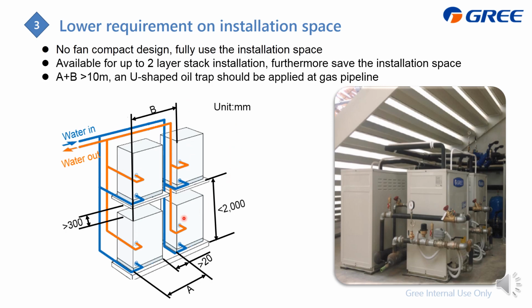In this case, you just need to pay attention to A plus B. If this distance is higher than 10 meters, you need to apply a U-shaped oil trap at the gas pipe.